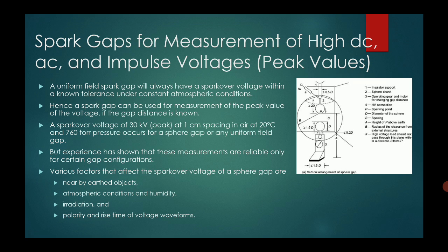One more important thing is spark gaps for the measurement of high DC, AC and impulse voltages. These give peak values, so spark gaps can be used for DC, AC and impulse voltages. A uniform field spark gap will always have a spark over voltage with a known tolerance under constant atmospheric conditions. Hence a spark gap can be used for the measurement of the peak value of the voltage if the gap distance is known. A spark over voltage of 30 kV at a 1 cm spacing in air at 20 degrees and 760 torr pressure occurs for a sphere gap or any uniform field gap.